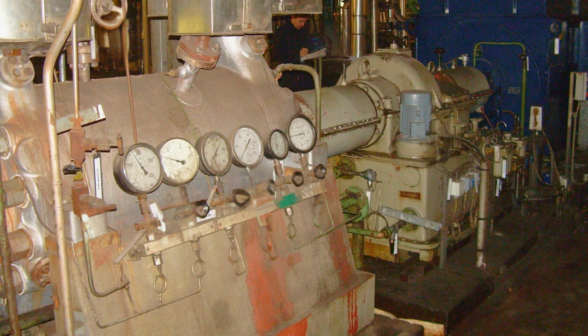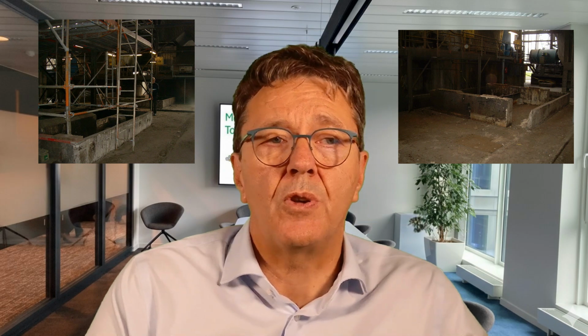The tender described the requirements for a medium voltage drive to power the existing 3 MW, 6 kV feed water pump motor. It seemed straightforward on paper — 6 kV motor, efficiency specs, basic electrical requirements. But when we got on site, we discovered there was actually no space at all in the electrical room for the drive system. We would need a dedicated housing and associated civil reworks.